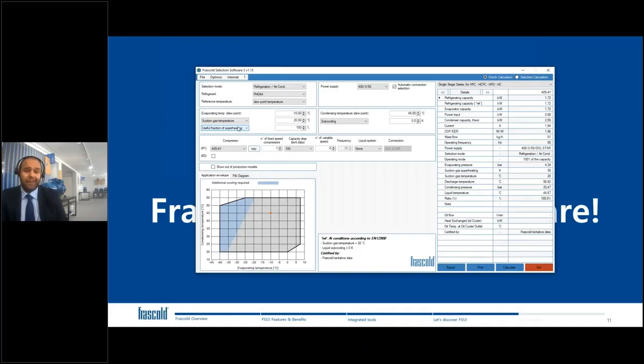The last box for suction condition is the useful fraction of superheating, so the part of the superheating that takes place in the evaporator. In this case, it is preset to 100%. So all the superheating for this system takes place in the evaporator and has a useful effect. You can clearly change this parameter, and you can set the evaporator superheating directly, so the Kelvin of superheating that take place in the evaporator. Same story, you have the same information in two different ways, depending on your preferences.